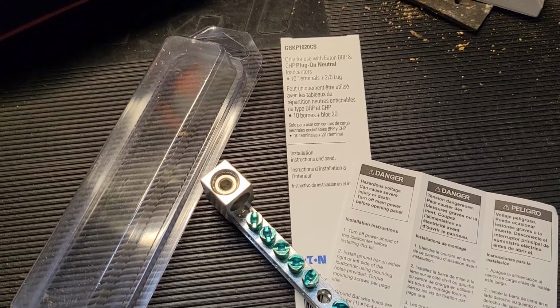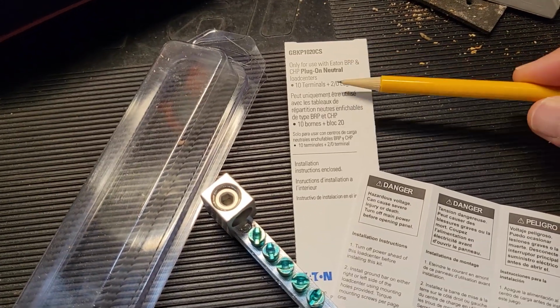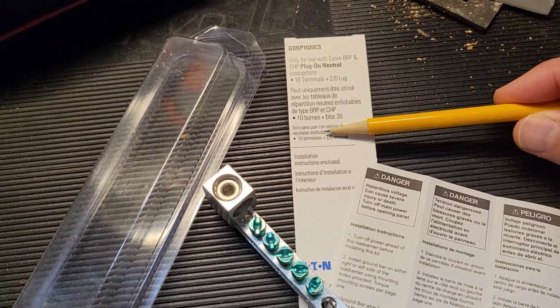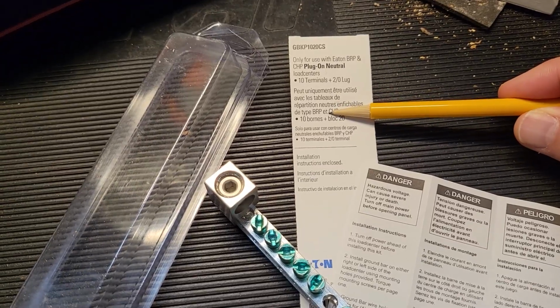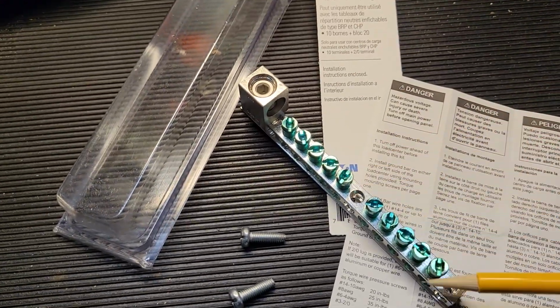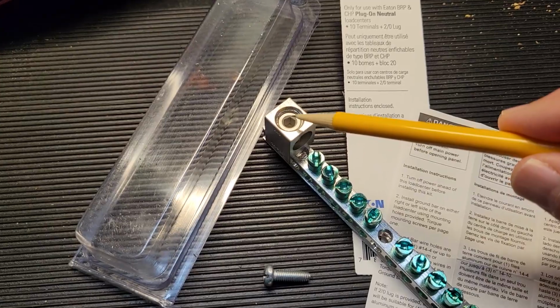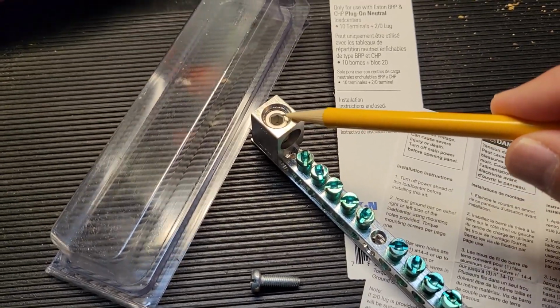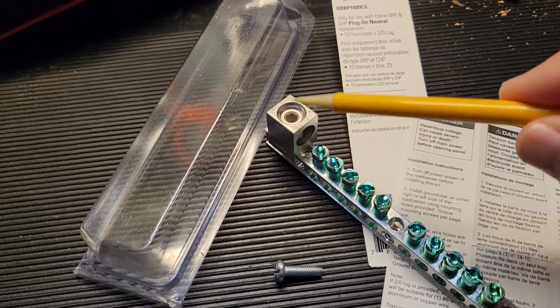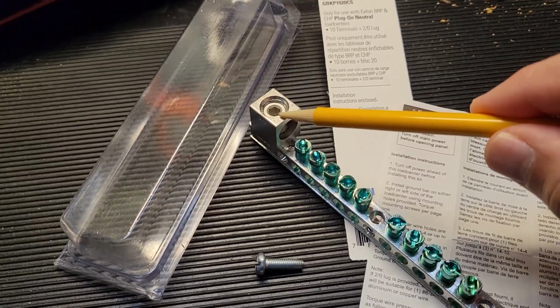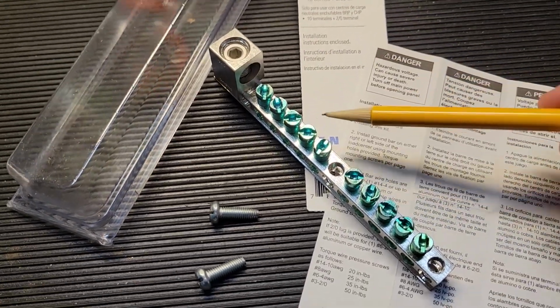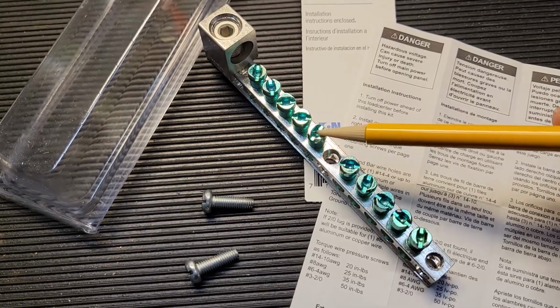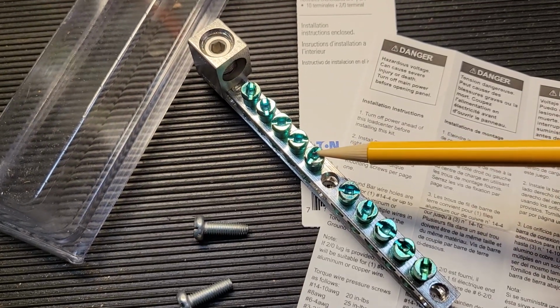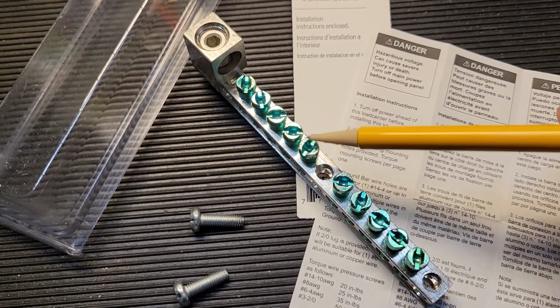Things to note about ground bars: they're made for specific panels, and that'll be on the packaging, so make sure you pay attention to that. Not all ground bars include the lug; sometimes that's sold separately, so make sure that if you need one, yours either comes with it or you purchase it. This ground bar's screws also have a square head, which is nice especially when you're torquing.